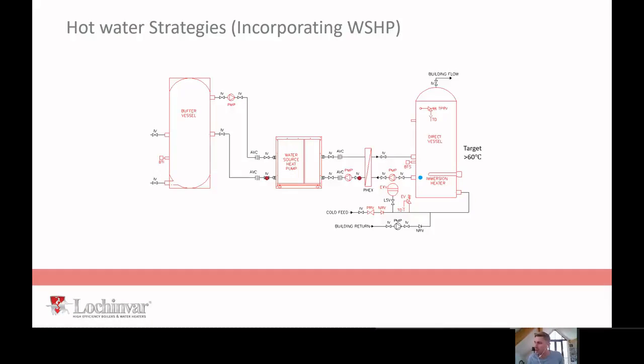I mean, if you've got a building with a load of waste heat, like server cabinets kicking out heat, and they're currently going to fans on a roof and it's ejecting to the atmosphere, don't eject it to the atmosphere, stick it into a thermal store if you can. Because if you then pick that up with your water source heat pump, if you're using waste heat, you've created a hot water application with a genuine efficiency in excess of like 500%. Now that's massive. A fifth of the equivalent running emissions you would have with a gas-fired water heater. It's quite an impressive feat, definitely.